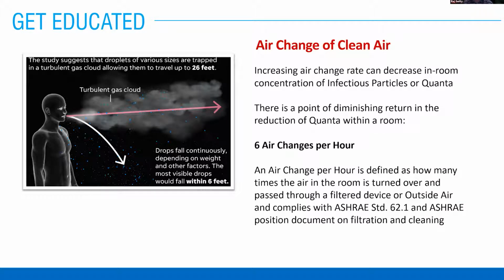With 6 air changes, we would like to see all of the air see a filter, get diluted, or get disinfected every 10 minutes. When your manufacturer literature comes out and says we're at a 99.9% kill rate, that is typically based on an hour of runtime, so you're going to see multiple passes. It also is not based on the increase of quanta. As you're seeing from the image below, as someone breathes, they're continually generating infectious particles. That has to be taken into consideration when you are thinking of your kill rate.